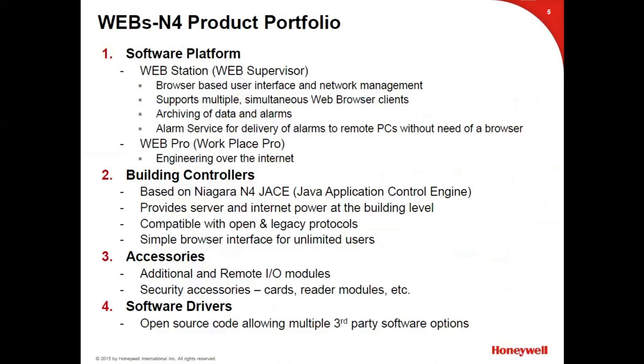Like with other JACEs, you can add I/O modules to the Web 8000 JACE. Third-party drivers can be added as well. We have an open Niagara architecture, meaning anyone's workbench will work on our Webs JACE. The Web 8000 uses a typical processor with available RAM, and it's fully encrypted. When you use FoxS protocol, that is an encrypted protocol. BACnet IP, by contrast, is not an encrypted protocol — that's a point we like to make. The drivers embedded in the JACE include BACnet, Modbus, LON, SNMP, and KNX.